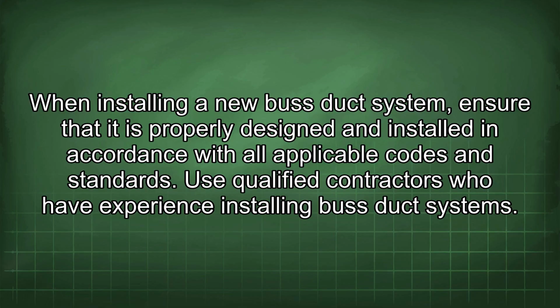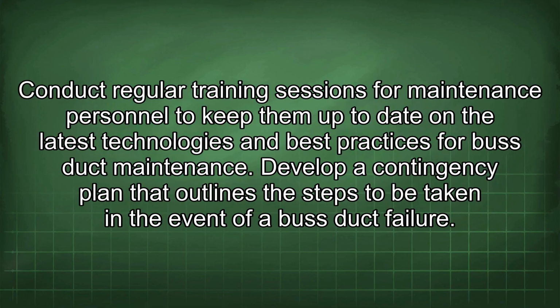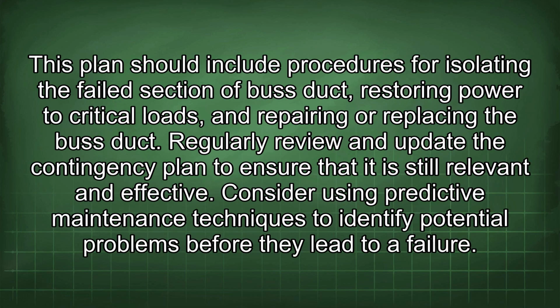Use qualified contractors who have experience installing bus duct systems. Conduct regular training sessions for maintenance personnel to keep them up to date on the latest technologies and best practices for bus duct maintenance. Develop a contingency plan that outlines the steps to be taken in the event of a bus duct failure. This plan should include procedures for isolating the failed section of bus duct, restoring power to critical loads, and repairing or replacing the bus duct.